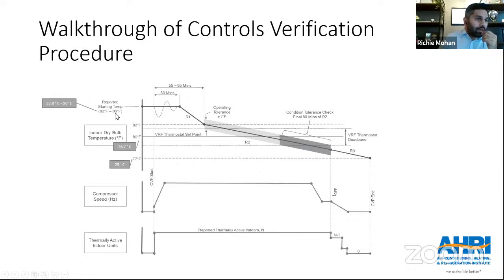This was of course taken from the AHRI standard 1230, which is why you see the IP units, but I've added units over here for your reference. To get through this overall walkthrough, the intention is that you install a VRF system in a test chamber, and you basically don't touch it at all. You simply modulate the test chamber temperature, which is going to be your outdoor ambient temperature.